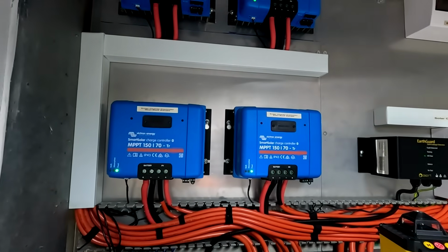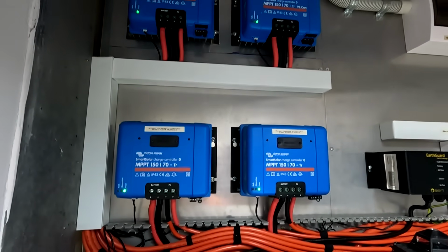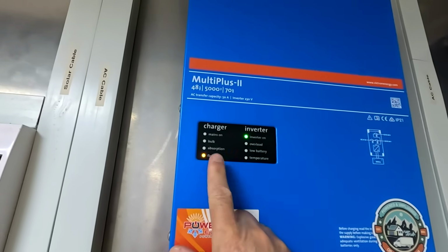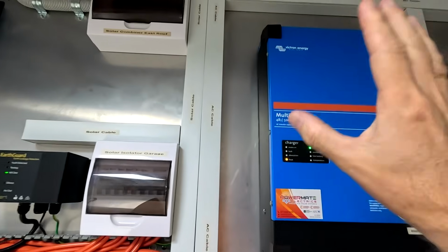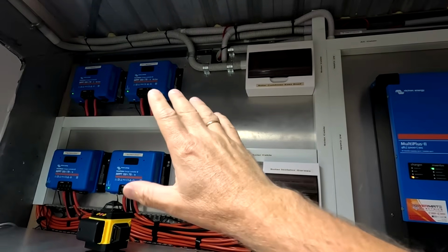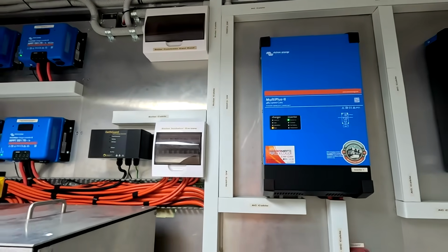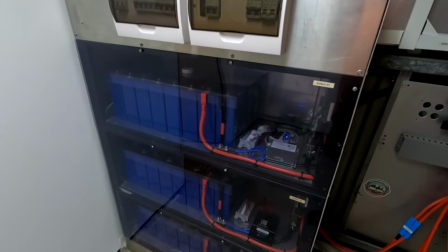So we are now in absolute float mode. All the lights are green on the MPPTs, and we can also see the float state here on the Multiplus. All the chargers, AC and DC, have now reduced the voltage to 53.6 volts, and we are not charging the batteries anymore at all. So for now we are all sitting at 100% state of charge and happily floating along.